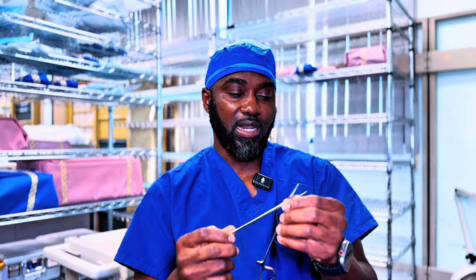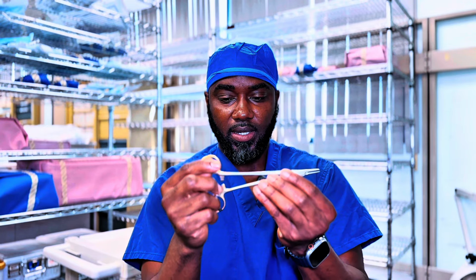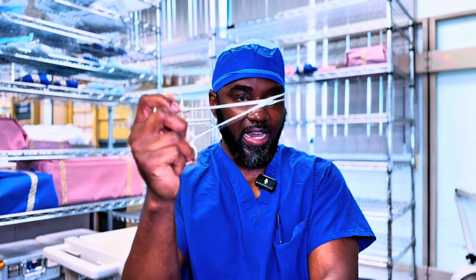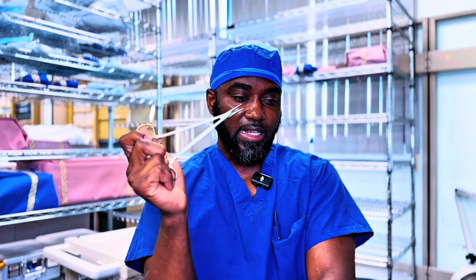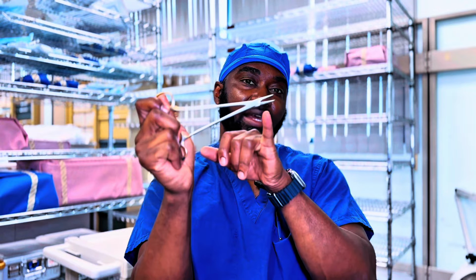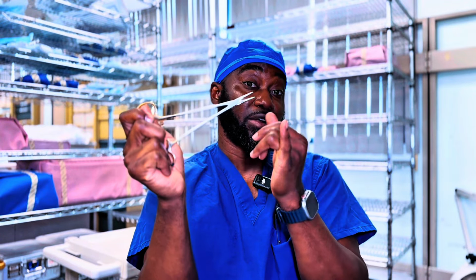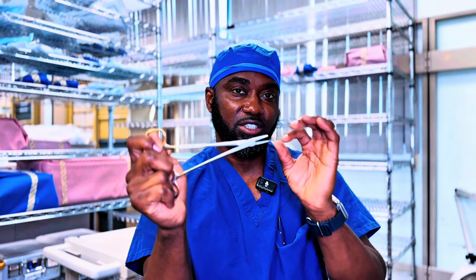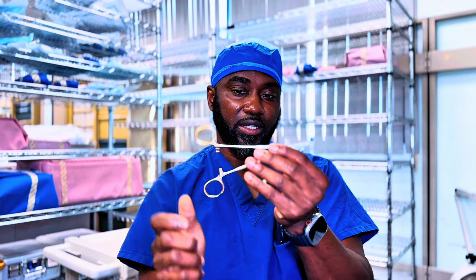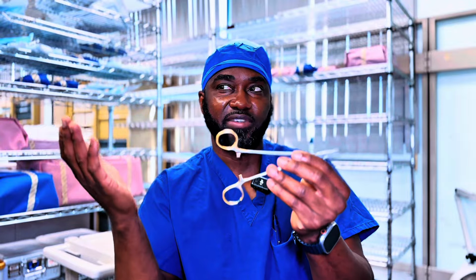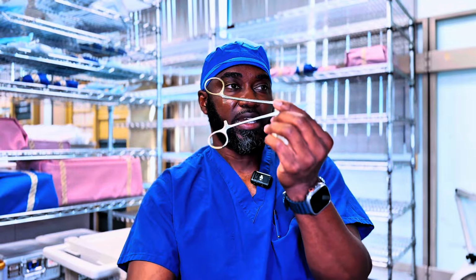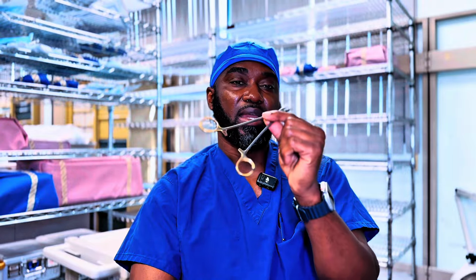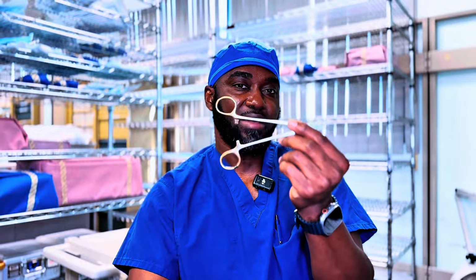Those tests will be done in an independent lab, and those labs will carry out processes called validation. In a validation process of any medical instrument, an independent lab will inoculate a medical device with microorganisms that might be pathogenic to the human body or that might cause harm to humans. The instrument will be inoculated and will be sterilized 3 separate times at half cycles.